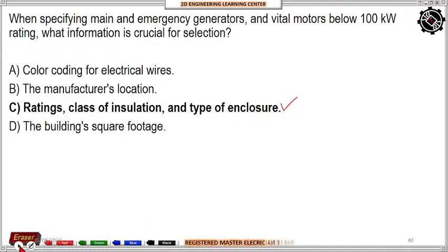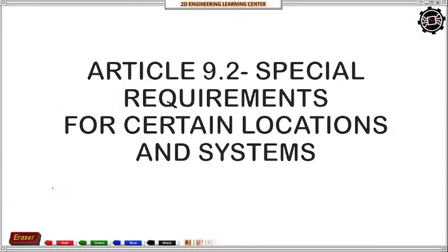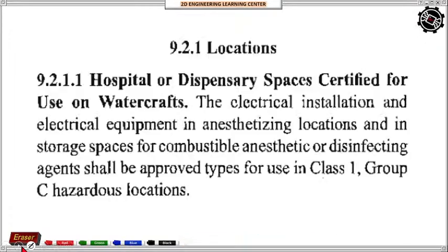Okay, next. So dito tayo sa Article 9.2. Special requirements for certain locations and system, no? Okay, so this is the specific requirements, no? So if in case our watercraft has a hospital or dispensary, no? So electrical installations and electrical equipment in anesthetic location and in storage spaces for combustible anesthetics or disinfecting agents shall be approved for use in class 1 group C hazardous locations.